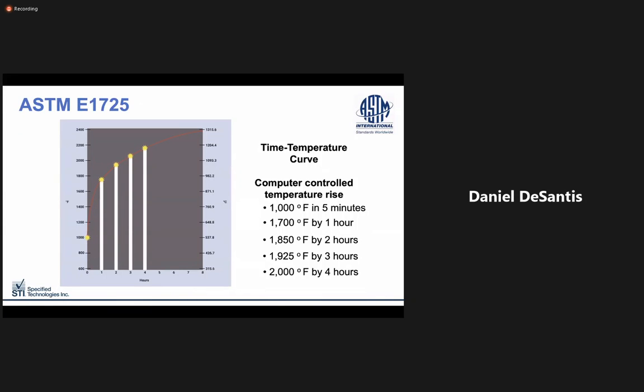So how do we know if a material is suitable for use as a fire-rated enclosure? Well, we burn it. Using the ASTM E1725 standard, a full-scale test is conducted in a burn lab. The temperature curve you see here is what's called the ASTM E119 temperature curve. This simulates real-world building fire conditions. The same time-temperature curve is used for through-penetration fire stopping, joint construction fire stopping, as well as curtain wall fire stopping.